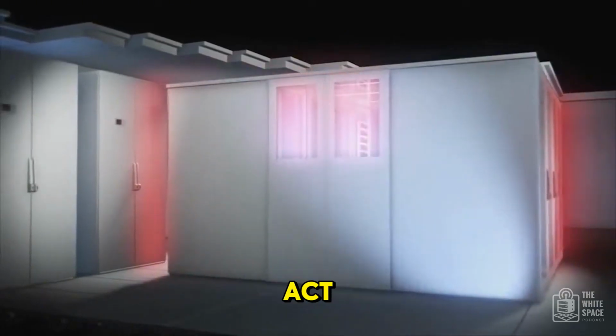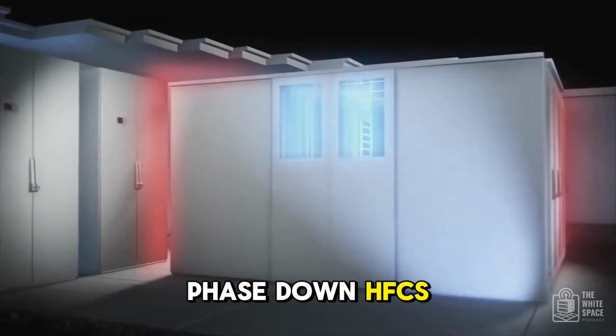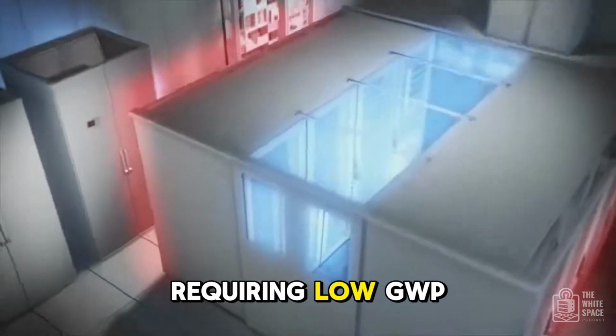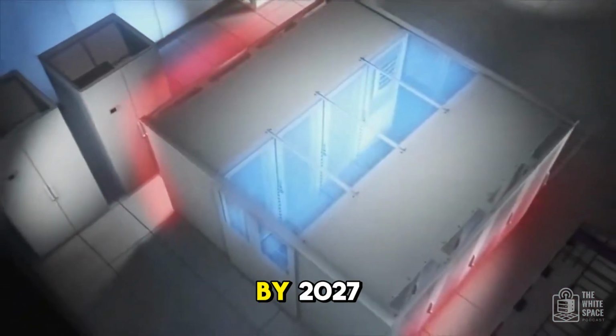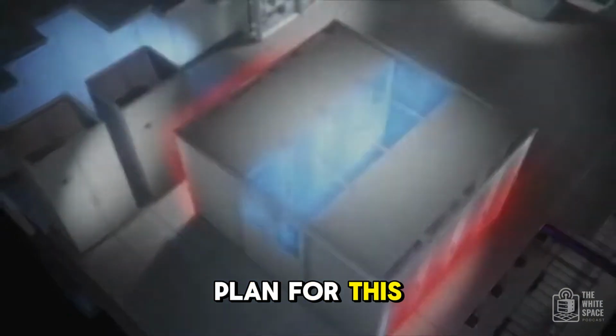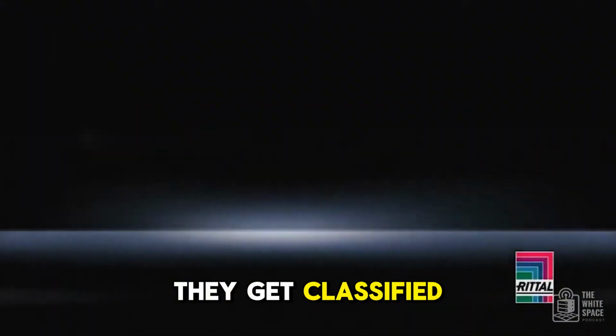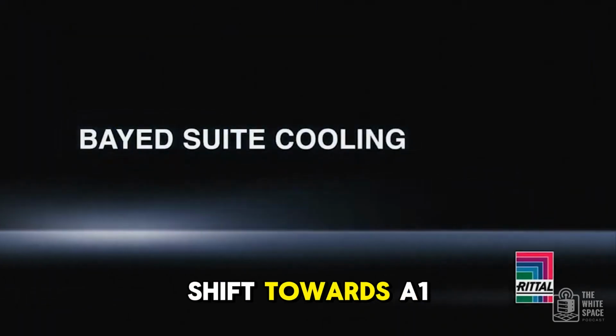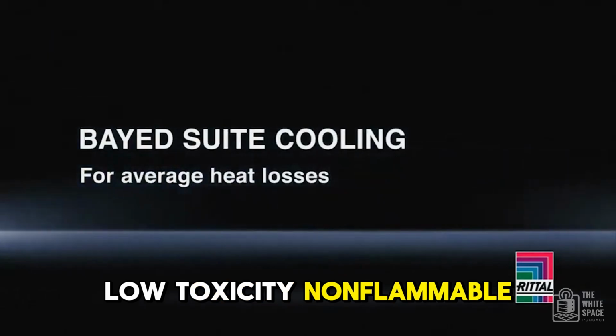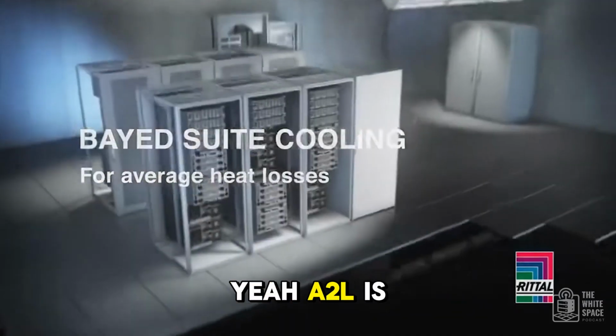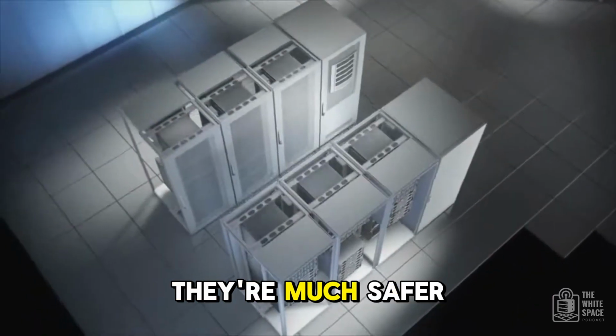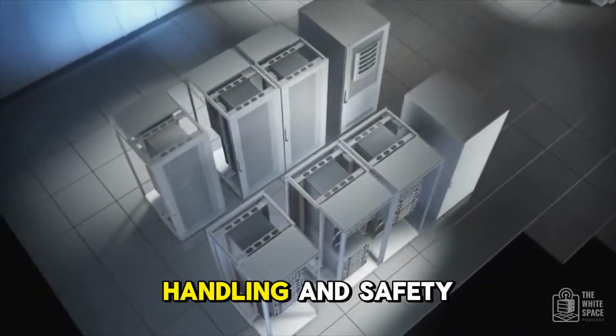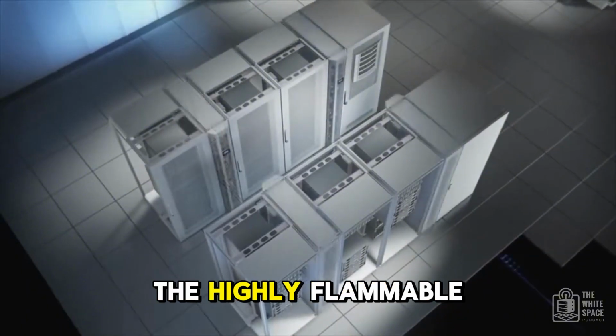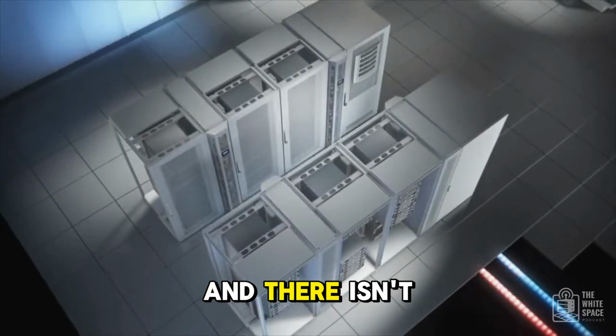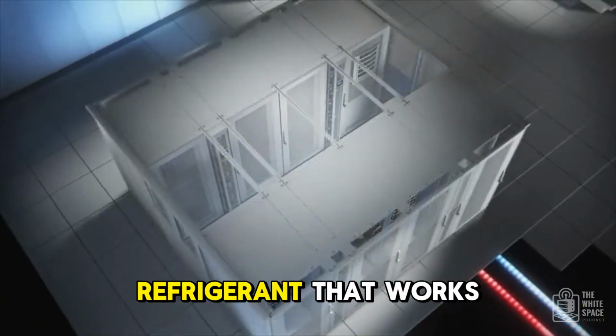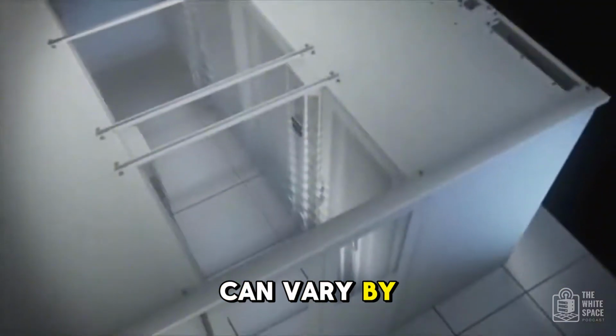In the US, there's the AIM Act. It gives the EPA authority to phase down HFCs, and similar rules are coming into effect, requiring low GWP refrigerants in new data center cooling gear by 2027 as well. Operators have to plan for this to stay compliant, and these newer refrigerants get classified by toxicity and flammability. We're seeing a shift towards A1 refrigerants, low toxicity, non-flammable, or A2L refrigerants. A2L? Yeah, A2L is a newer classification for mildly flammable. They're much safer than older flammable options, but require specific handling and safety measures. Data centers are generally avoiding the highly flammable stuff like propane that you might see in a domestic fridge, and there isn't one single perfect low GWP refrigerant that works everywhere. What's acceptable or preferred can vary by region due to these regulations.